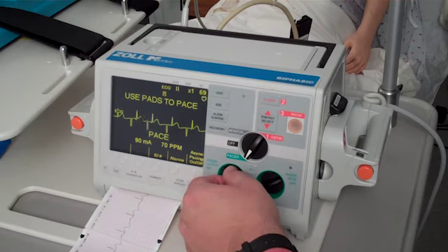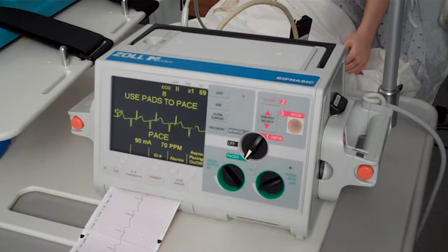Once capture is achieved, decrease that setting to the lowest energy required to maintain capture. Check the patient's pulse to make sure that there's also mechanical capture and not only electrical capture.